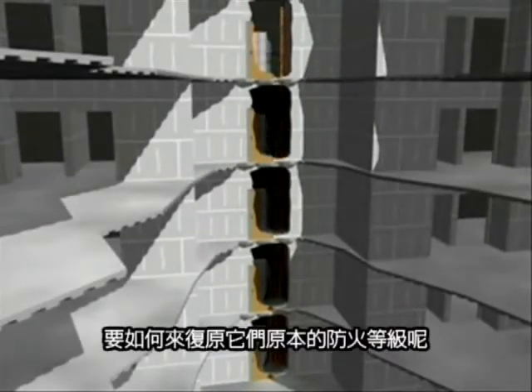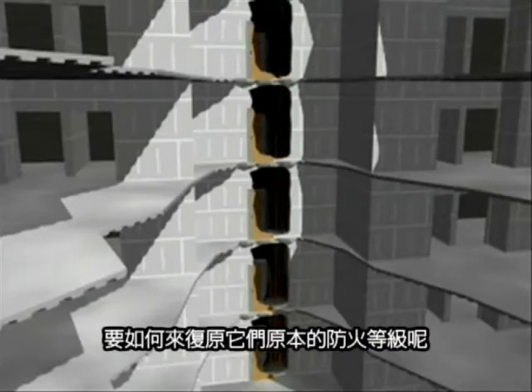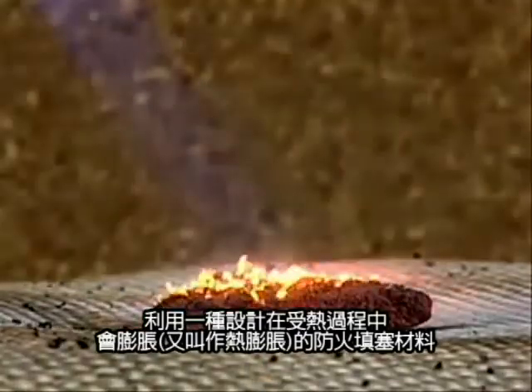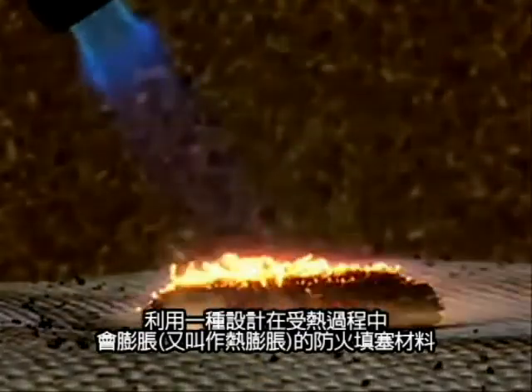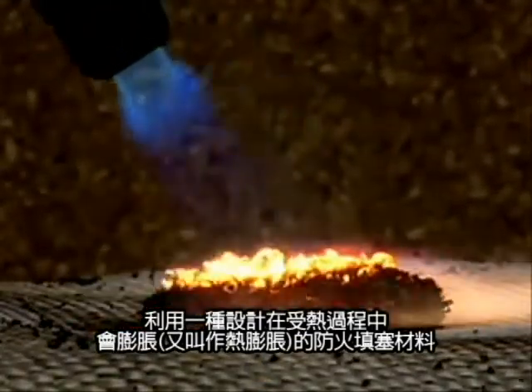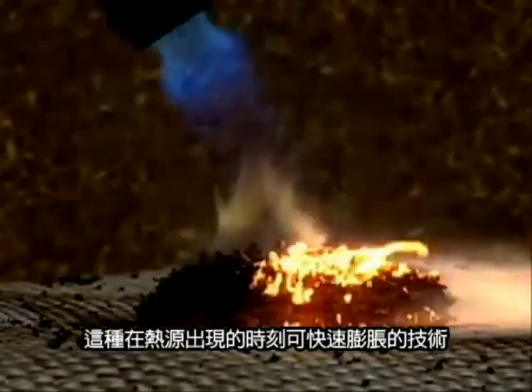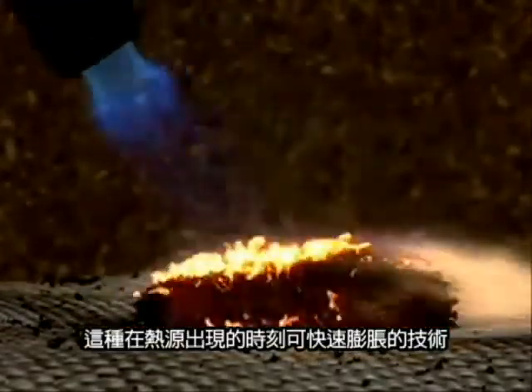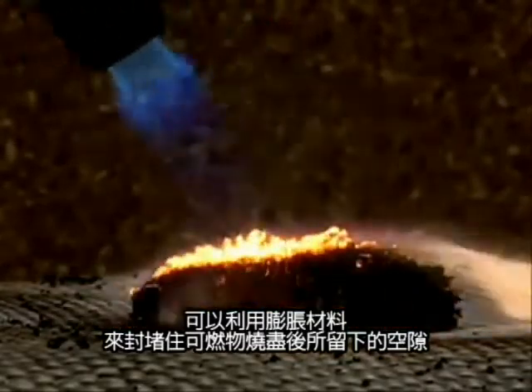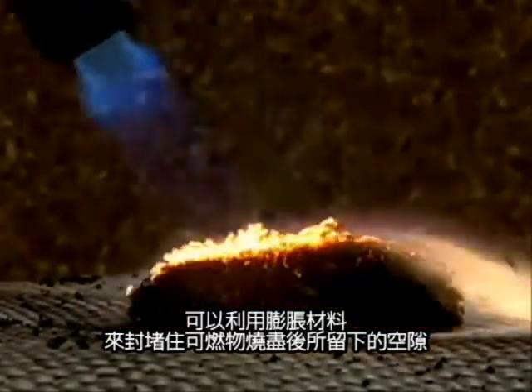So, how are combustible penetrations in a fire barrier restored to their original rating? By using fire-stop materials designed to expand with heat in a process called intumescence. This technology permits rapid expansion in the presence of heat so that voids created by the melting combustibles can be sealed by the intumescent material.